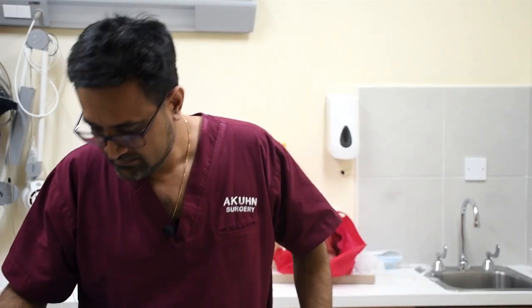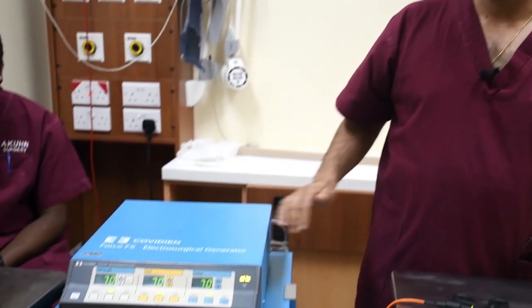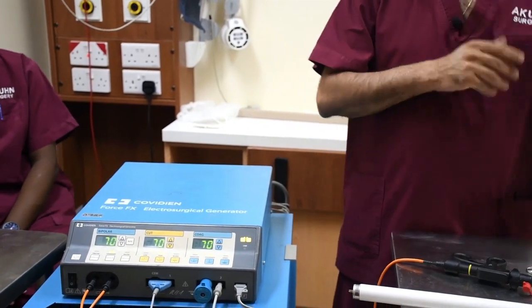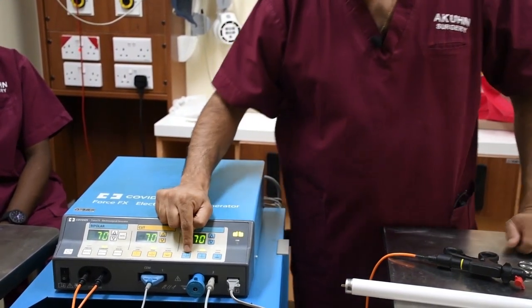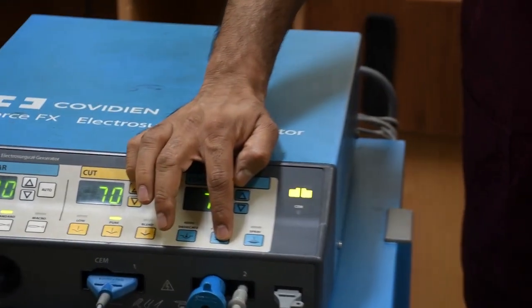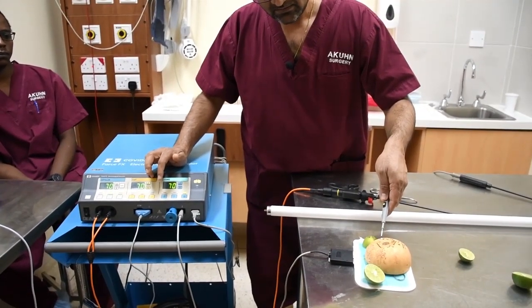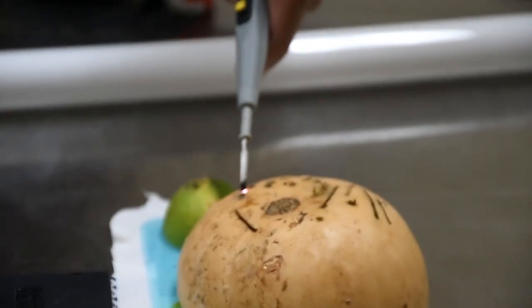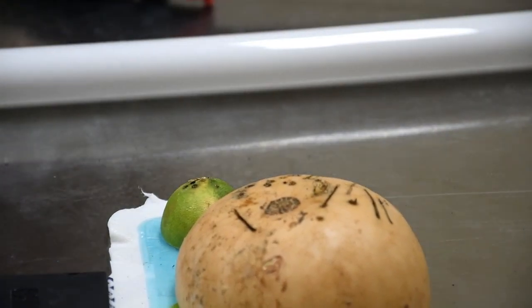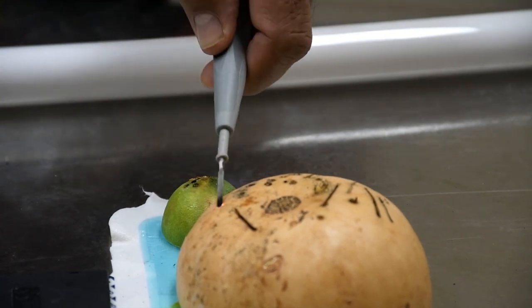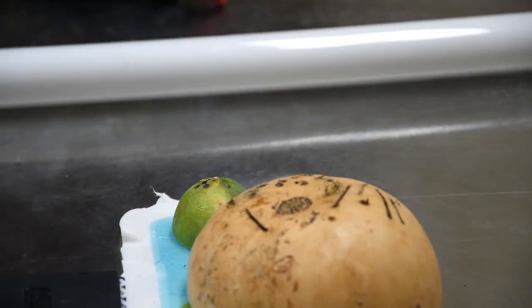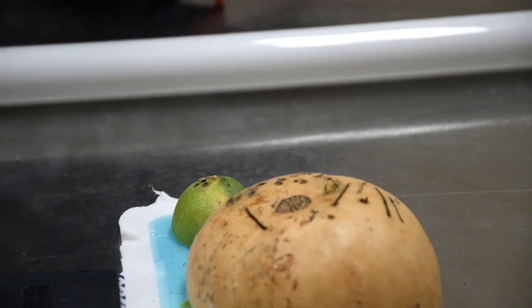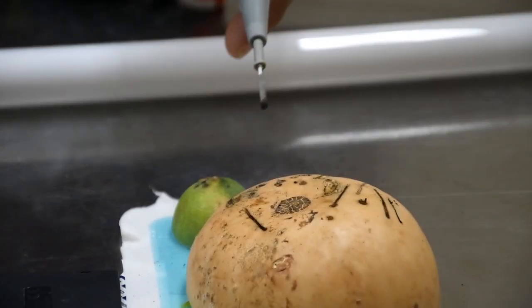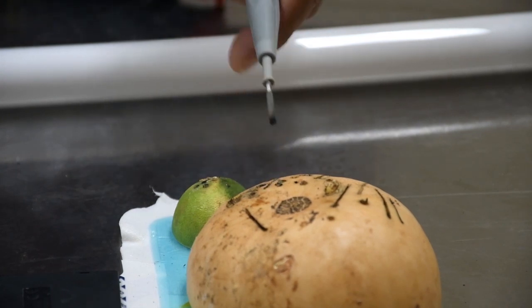When I go to blend, so let's go to the other side, we say the coag, it is active only 4 to 6%, but it's very high voltage. In that you have desiccate, you have fulgurate, so this is fulgurate and this is spray. See the difference? So you can hear there is a different sound and it's spraying over superficially. Whereas when I go desiccate, it will not do that. It is now drying it up. So there is a difference in the effects that we see by this. So fulgurate, spray.